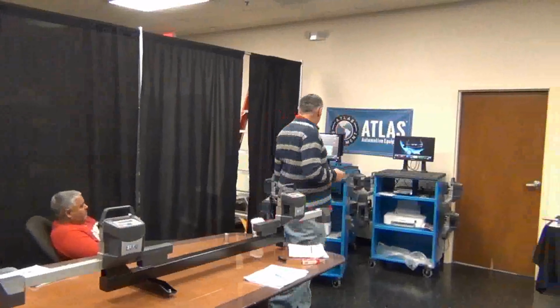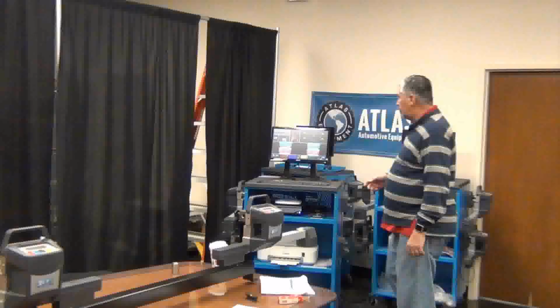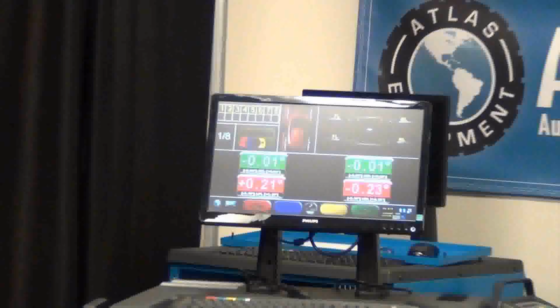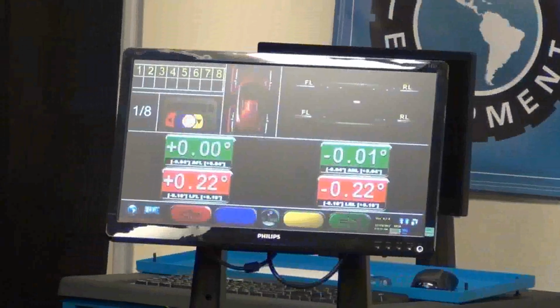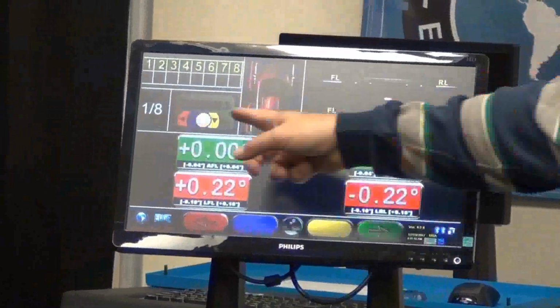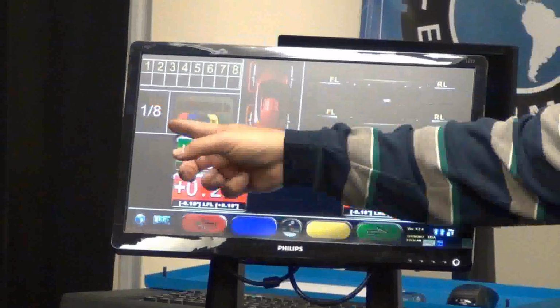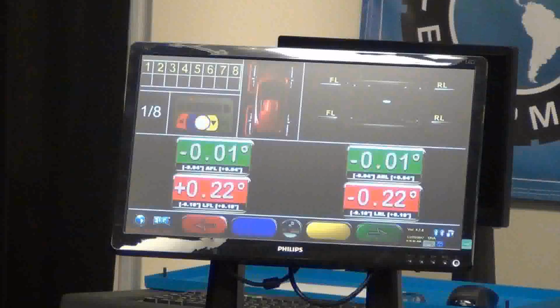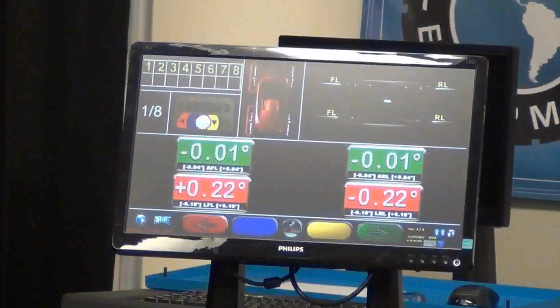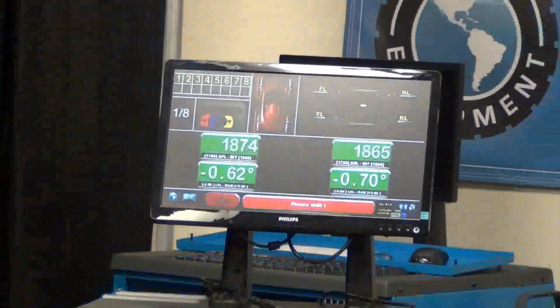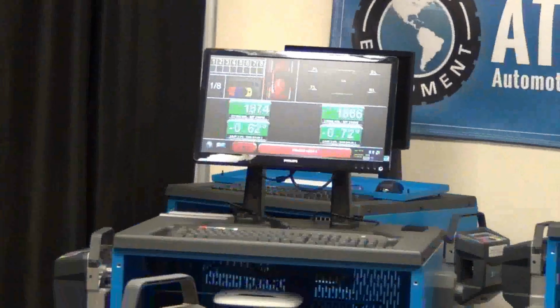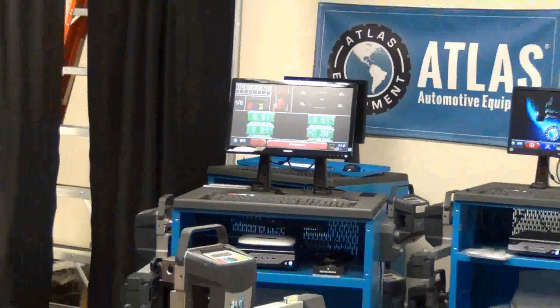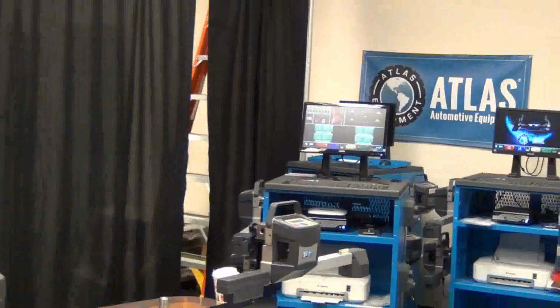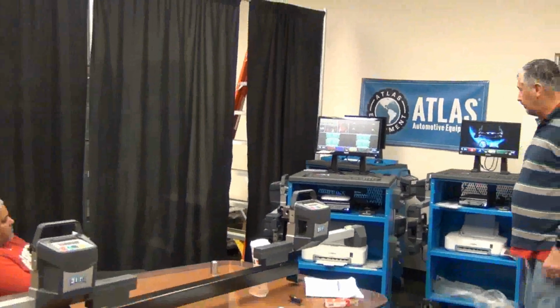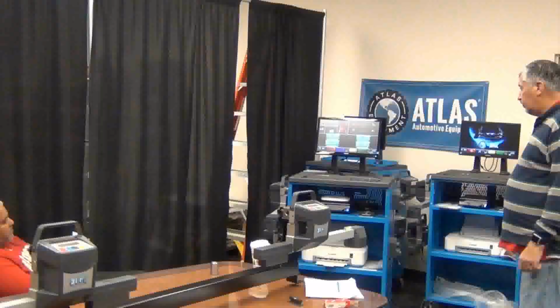Now, if you look at the machine, it shows you your existing calibration situation. So what you do now is, you see the little flashing light, we are in position 1 of 8. We have 8 steps we are going to perform, and we are in position 1 of 8. Now I hit the black button in the center. The machine takes everything down to 0. See how the numbers have moved down to 0? All numbers have now moved to 0.